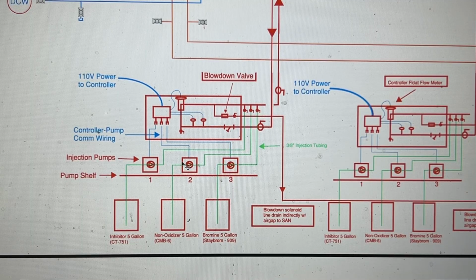the pumps. So there's a pump shelf with 3 different pumps serving the inhibitor, non-oxidizer, and the bromine. The controller, obviously self-explanatory, controls how much chemical gets added to this loop. And every so often, this blow down valve, this solenoid valve, will blow down to drain as well.